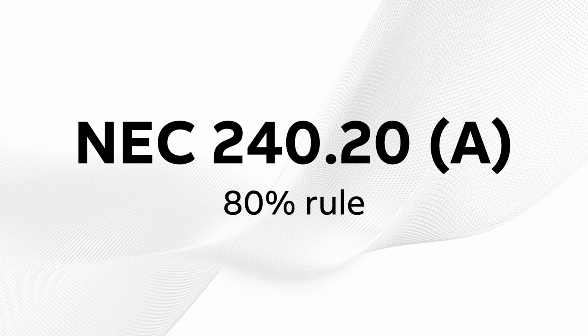The circuit breaker is designed to carry 100% of its current rating, but the NEC restricts the application for continuous loads to 80% of the circuit breaker's rating. There are 100% rated breakers that have been tested and labeled for use at 100% of its continuous current rating. Otherwise, a breaker may only have a maximum of 80% of its labeled continuous current rating.